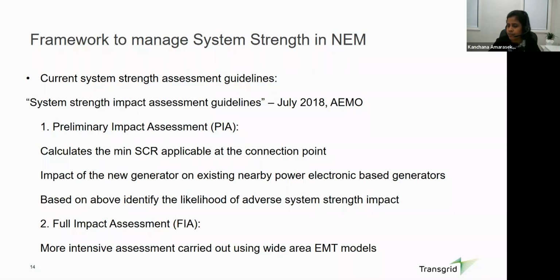It is to see whether they can stably operate at that condition. So that's the target of the first criteria. The second criteria is that when a new generator tries to connect, there are a number of other generators in the surrounding network as well. These generators are also usually grid following generators, and they need adequate system strength to operate. So we also check the impact of the new generator on these existing nearby generators. And this PIA, or Preliminary Impact Assessment, is a very high-level screening assessment. It only looks at the minimum fault level and the SCRs, and based on that, it tries to identify the likelihood of any adverse system strength impact. So it's like a screening process. If the SCR is quite high and there are not many plants around, we can usually say it's okay. But if it is not okay, those generators will have to go to a second stage.